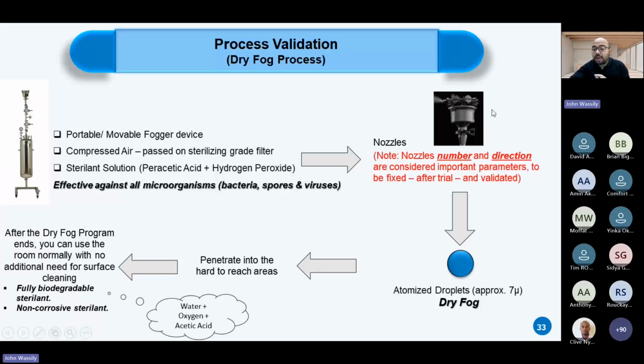The nozzle number and direction are very important parameters, because based on those nozzles we get a fogged solution of atomized droplets of the sterilant solution, approximately 7 micrometers in size. These droplets act as a dry fog, decontaminating even the hardest to reach areas within the clean rooms and grade A and B areas. After the dry fog program ends, you can use the room normally with no additional need for surface cleaning, because the mixture of peracetic acid and hydrogen peroxide is fully biodegradable and non-corrosive, finally degrading into water, oxygen, and acetic acid.